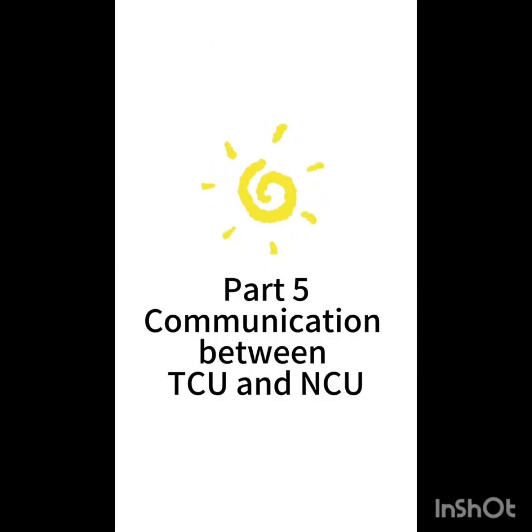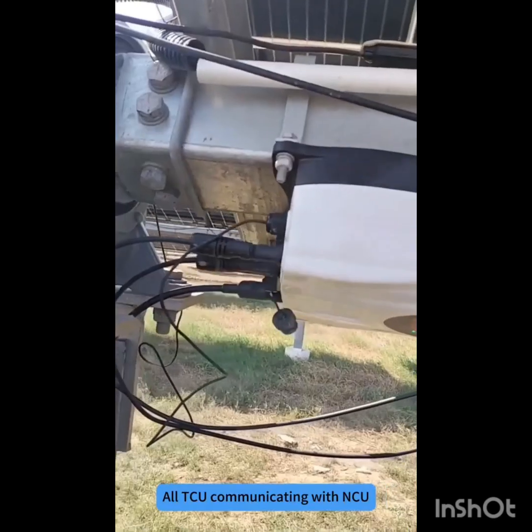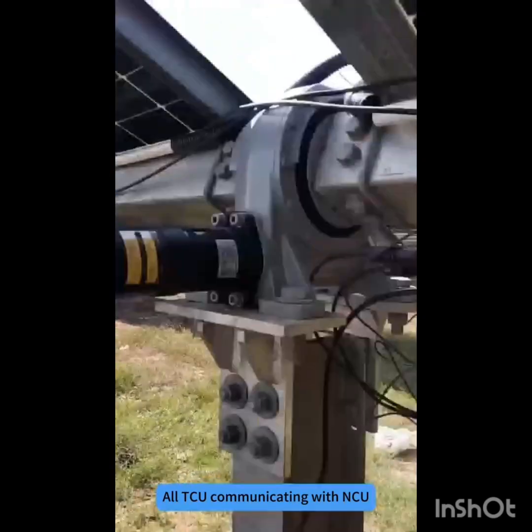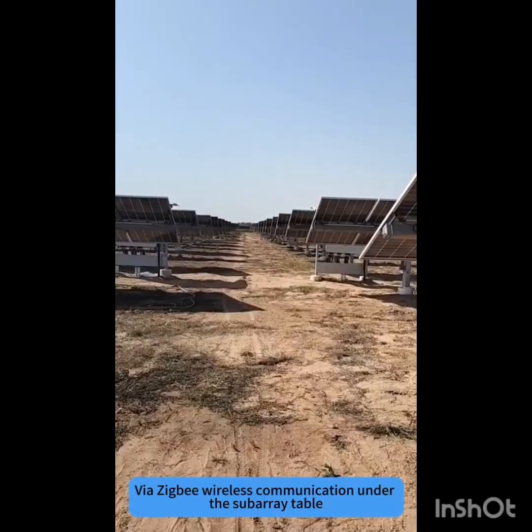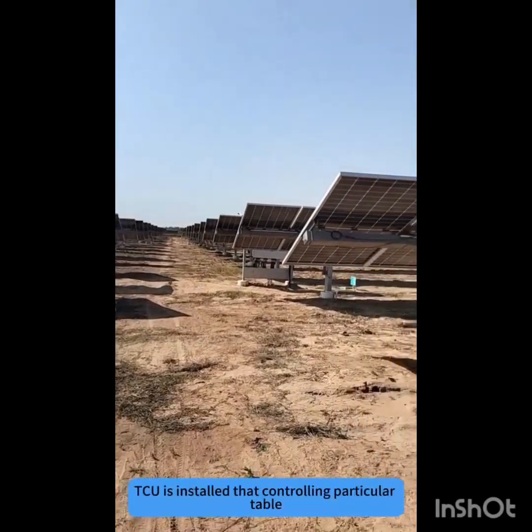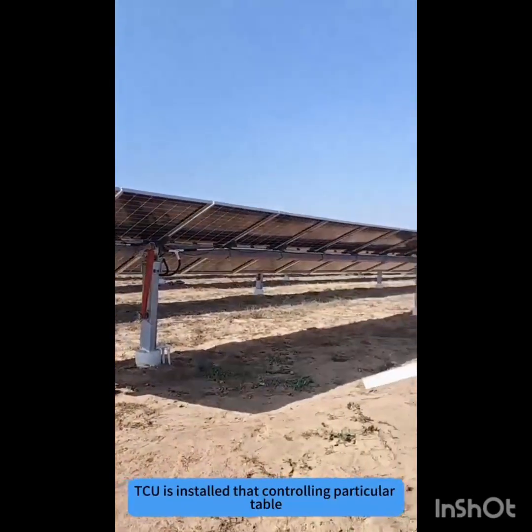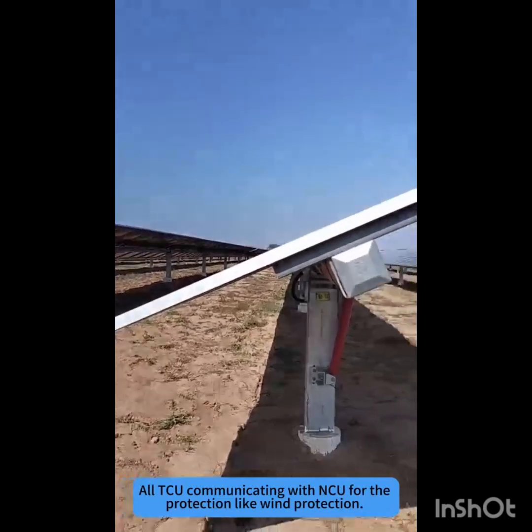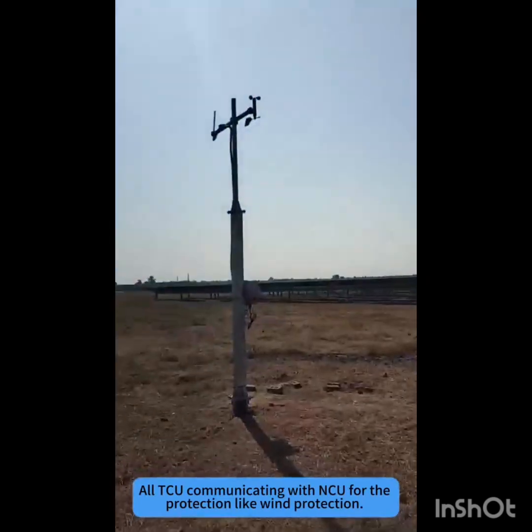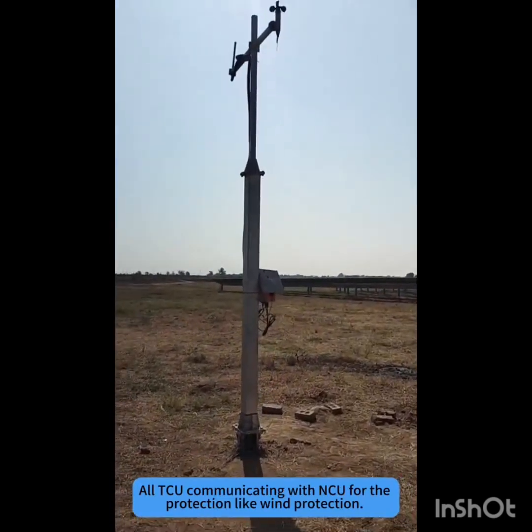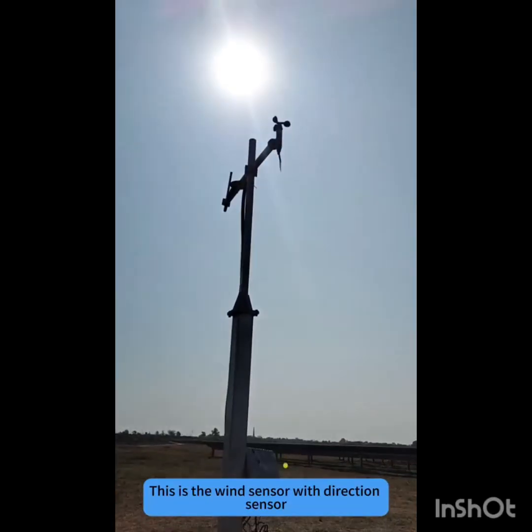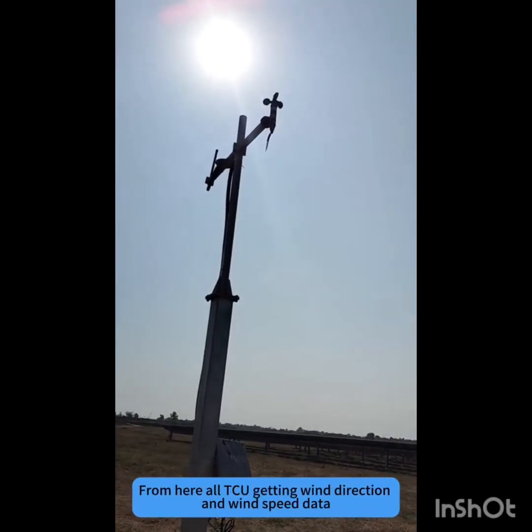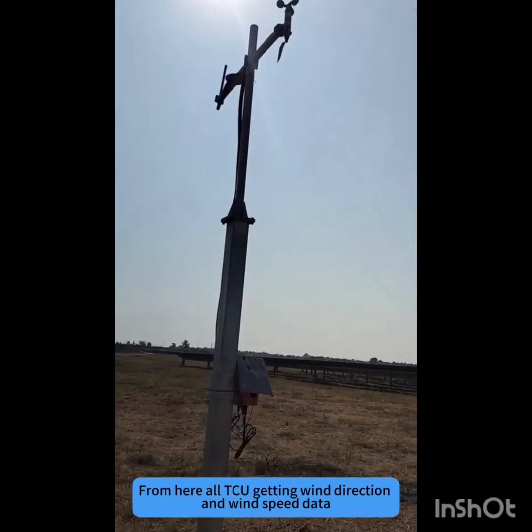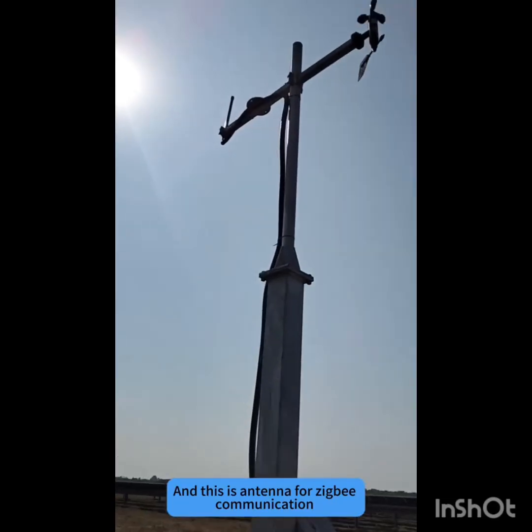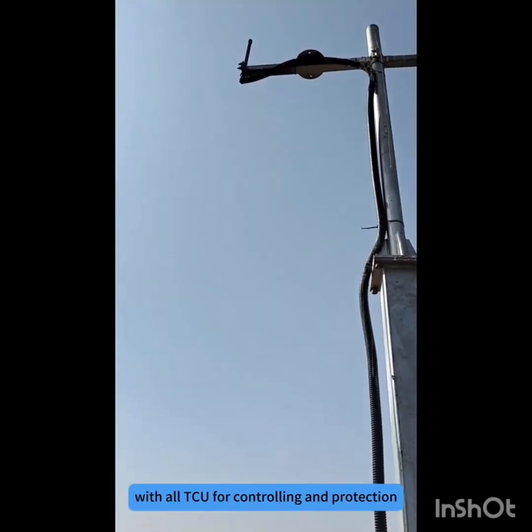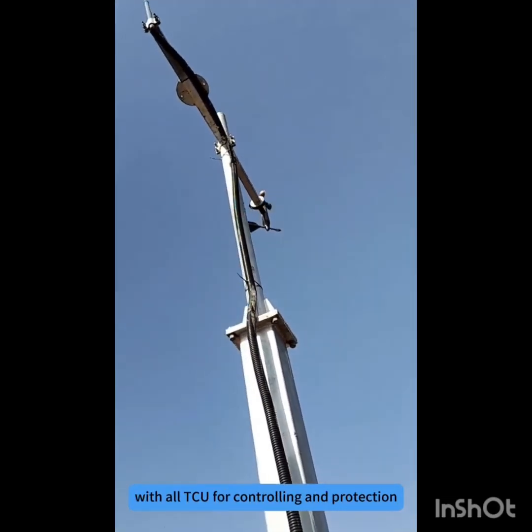Part 5. Communication between TCU and NCU. All these TCUs are communicating with the NCU by Zigbee wireless communication. Under every table one TCU is installed that controls that particular table. All TCUs communicate with the NCU for protection, like wind protection. This is the wind sensor with direction sensor. From here all TCUs get wind direction and wind speed data. And this is the antenna for Zigbee communication with all TCUs for controlling and protection.